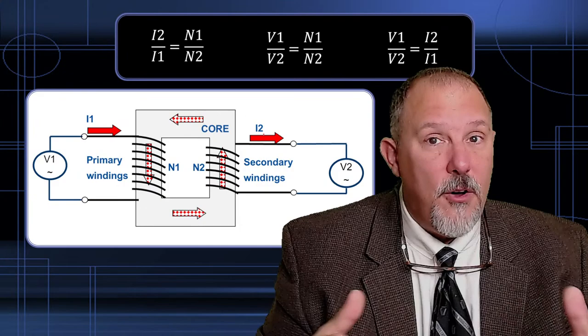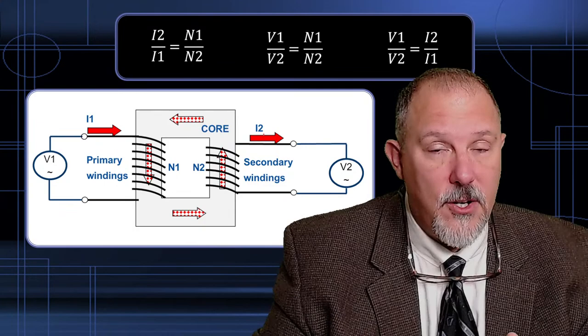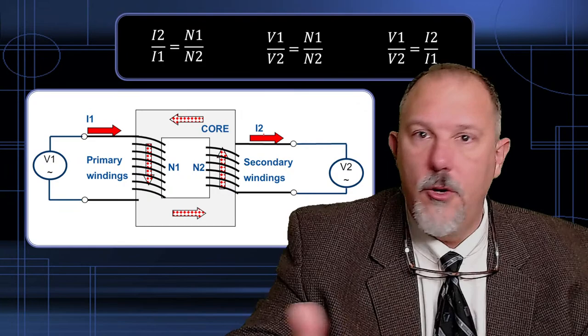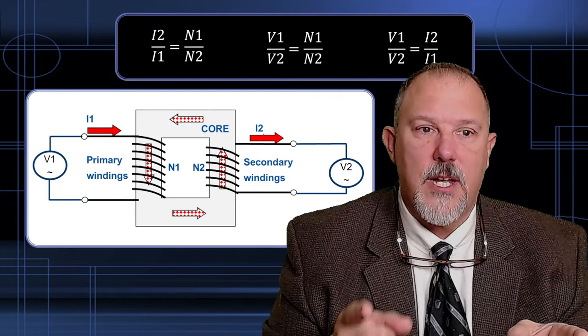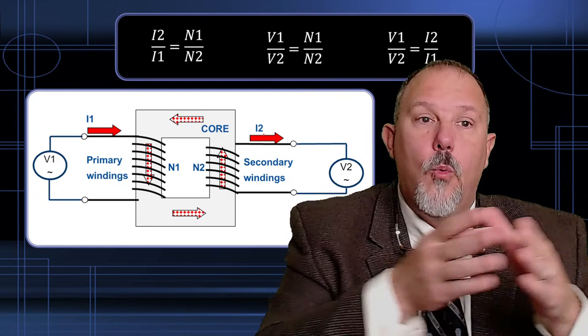And whether it's a short circuit that they're supplying current to or a lower than full load amps load current, there will be a transposition. I can use these equations to understand for any given value of current on the secondary of a transformer, what is the expected current on the primary of a transformer.